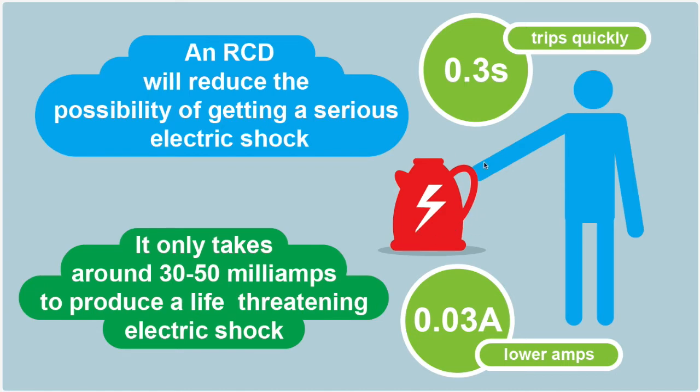Anything above 0.03 of an amp can start becoming dangerous to life, and the RCD trips very quickly. So that's what the RCD does—it trips power at a much lower rate than a normal MCB and trips very quickly. It's a very good device for additional safety in your electrical installation.